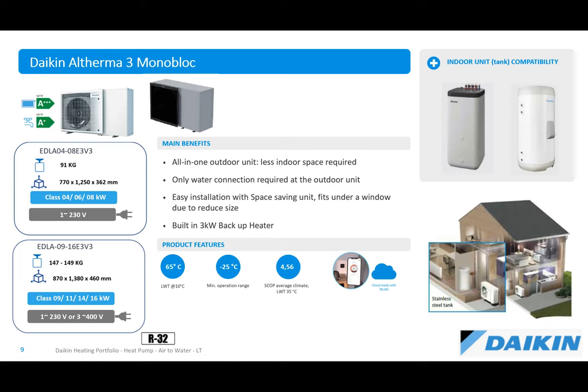So the monoblock range starts at a 4 kilowatt, which is for a small building, all the way up to 16 kilowatt. You can see two different images there of outdoor units. So the smaller white one is the smaller class, 4, 6, and 8 kilowatt. The one with the black grill is 9, 11, 14, and 16. This is a new product that was launched. Both of them have R32 refrigerant, both launched in the last year. And the higher classification ones would ordinarily have been a double fan unit. They've been redesigned now into a single fan unit, so they fit under a window, which makes it quite convenient for locating the outdoor unit and keeping it close to the house as well.